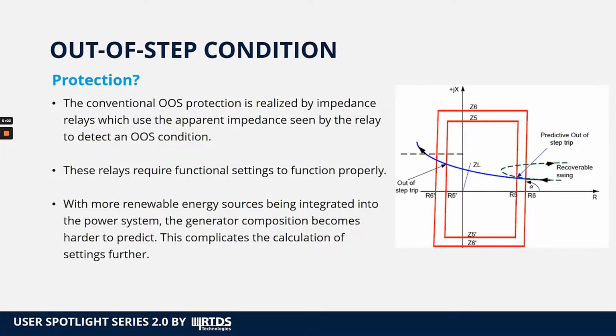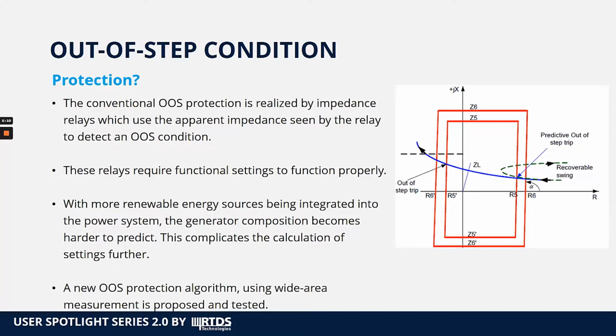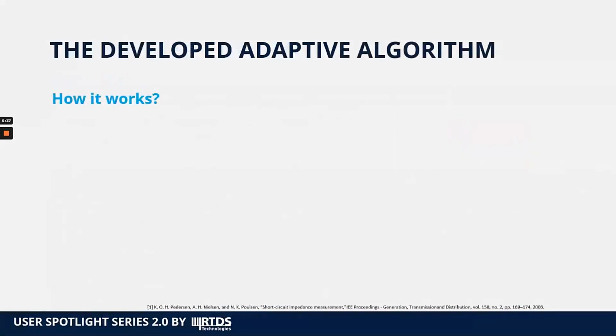So this made us think, how can we improve this? And we developed a new out-of-step protection algorithm using wide area measurements that does not require any settings or requires minimal settings. And we tested it using hardware in the loop simulations and compared it to the traditional impedance-based relays. So moving on to the developed protection algorithm, how does it work?